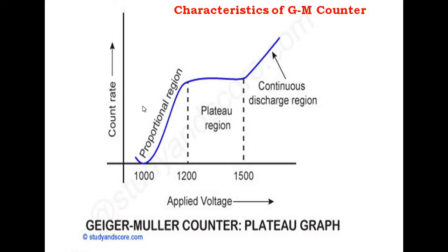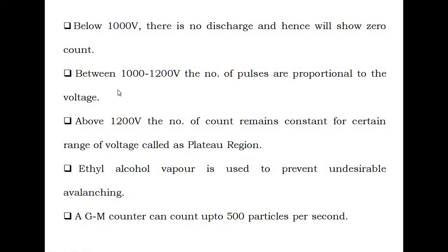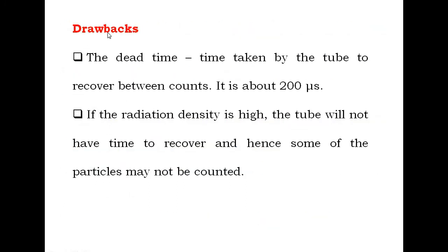There is a drawback as well. The main drawback of the GM counter is dead time — the time taken by the tube to recover between counts, which is about 200 microseconds. If the radiation density is high, the tube will not have time to recover and hence some of the particles may not be counted.